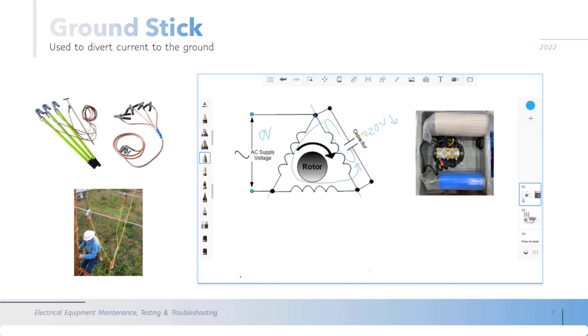So how do we discharge this capacitor? This is why we use ground protective equipments. If you connect the ground protective equipment to this terminal and connect the ground protective equipment to the ground, a current will flow. If this is the positive, it will flow from here to the ground, here to the ground, creating a short circuit in this capacitor, so this capacitor will discharge quickly. So after that you can operate in the terminals safely.